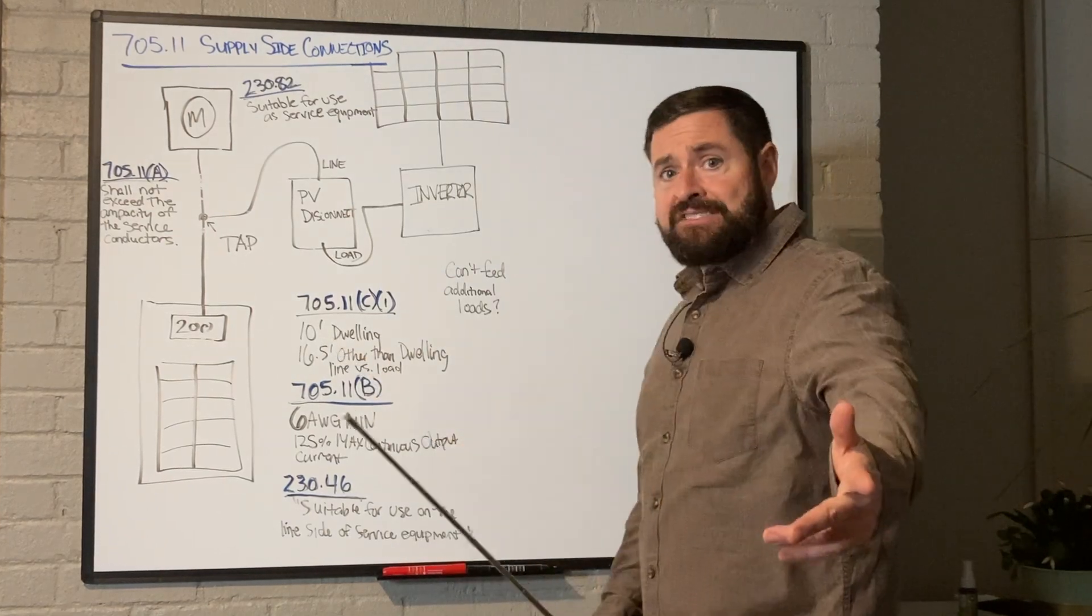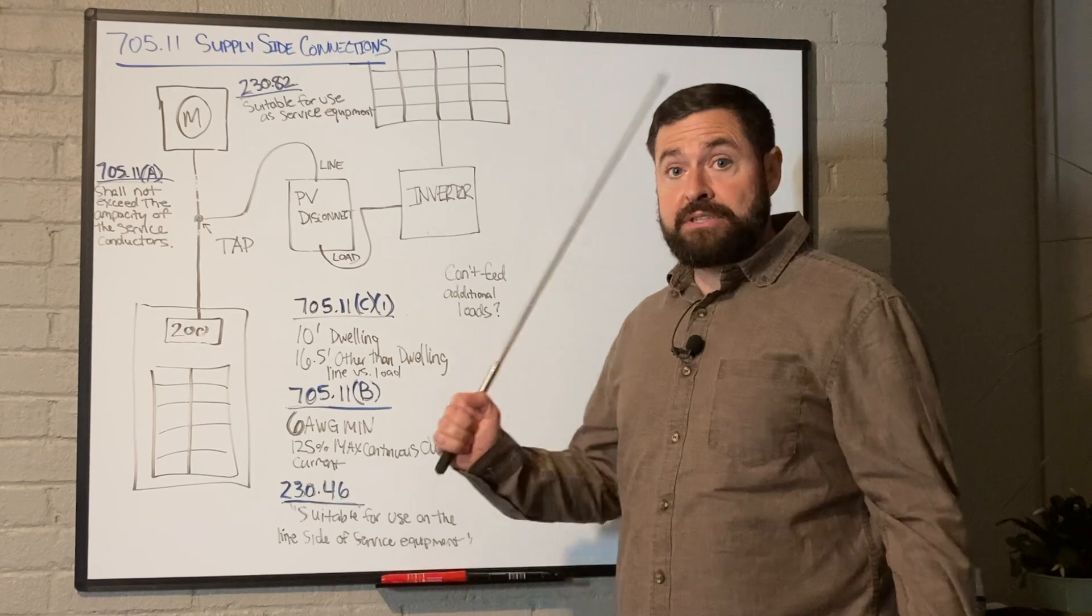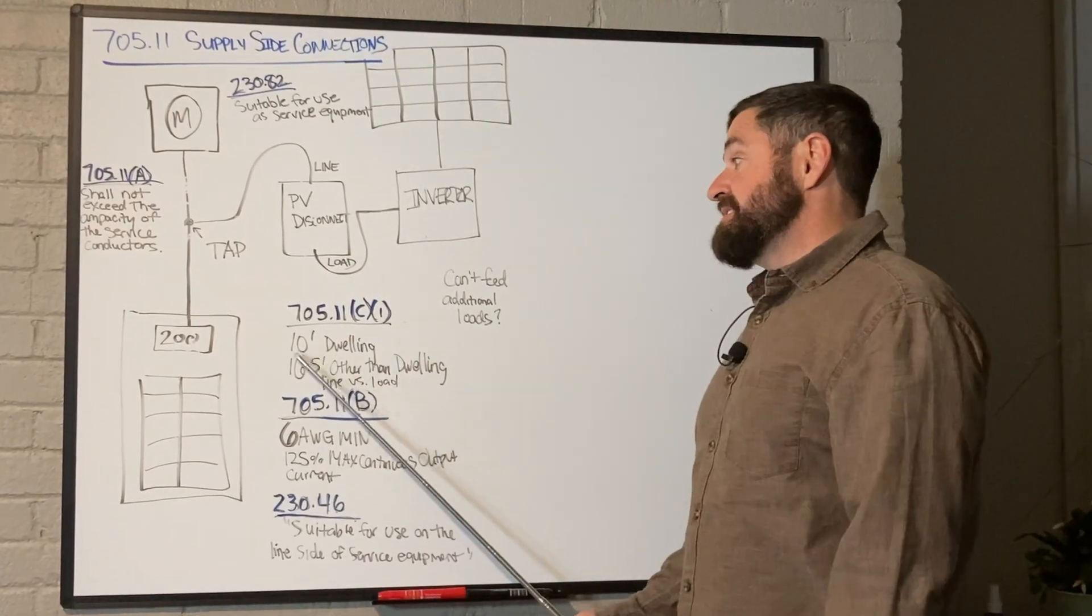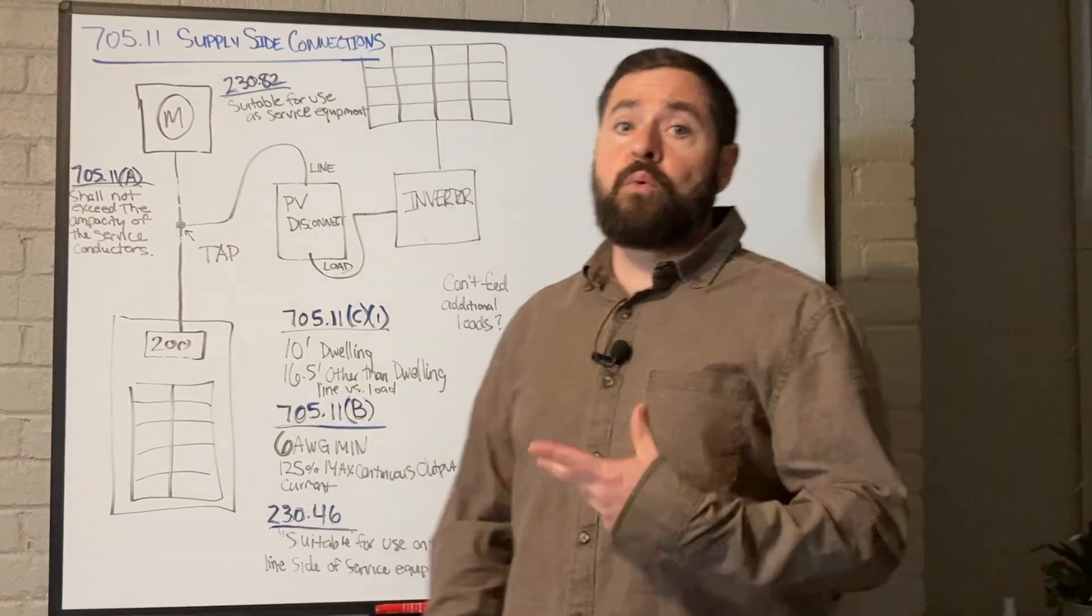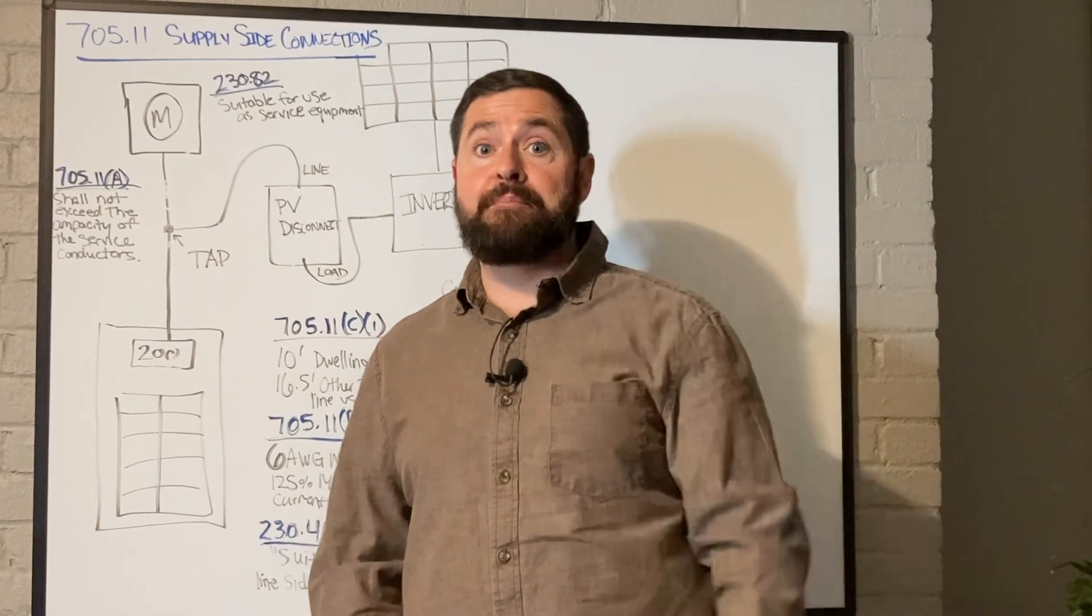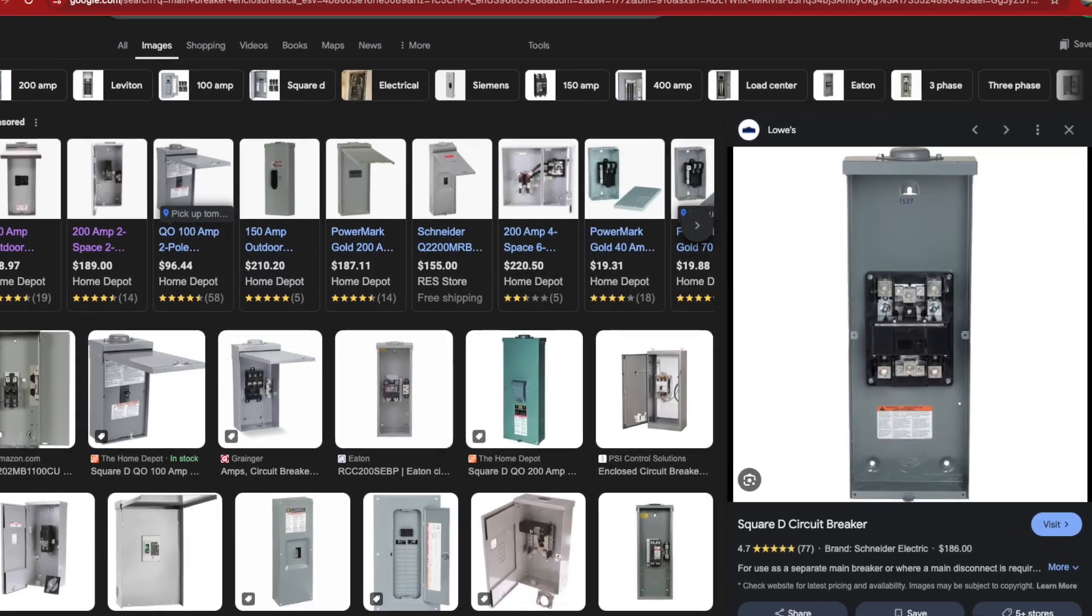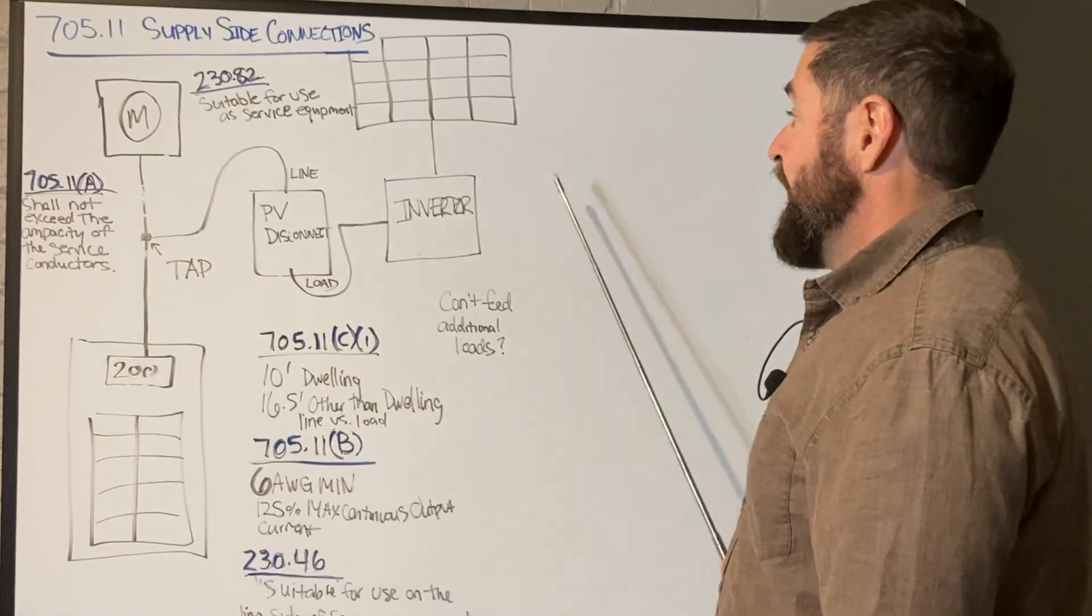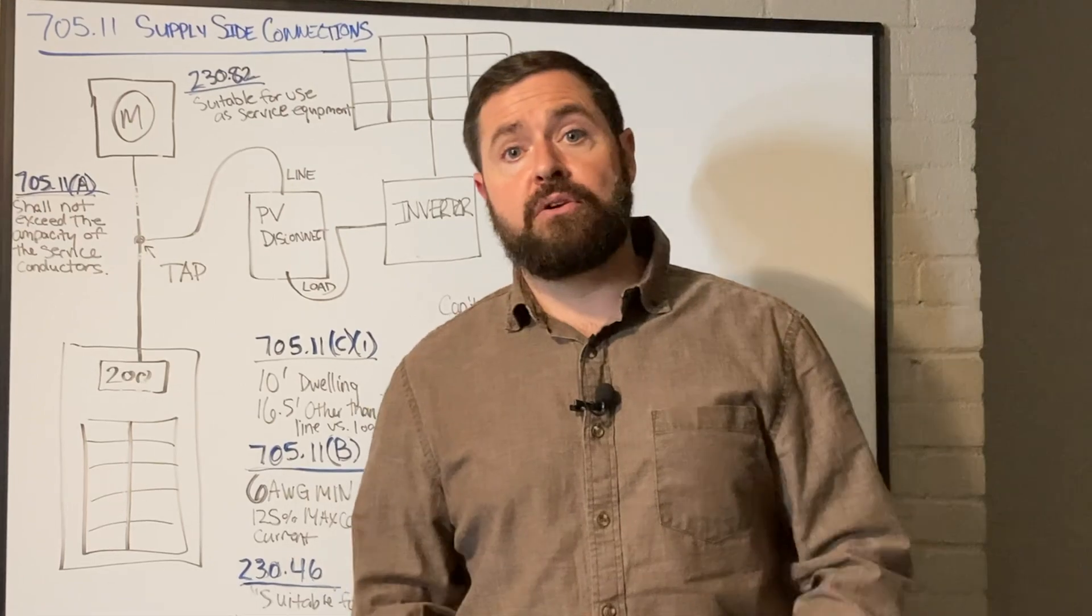So if you get into a situation where you're doing a tap inside and maybe you need to put the PV system disconnect outside by the meter and that exceeds the 10 or the 16.5 feet, what a lot of people will do is put two disconnects: one by the tap, either a main breaker enclosure or a fuse disconnect, and then from there add another non-fuse disconnect outside by the meter. A lot of utilities require that or maybe AHJs.